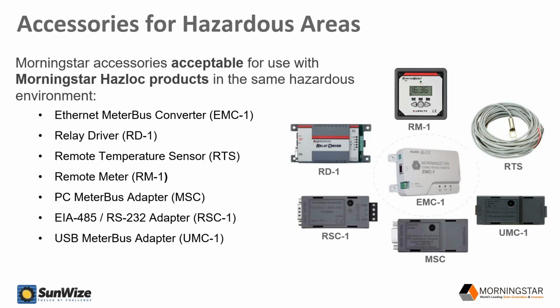In other words, these products have gone through the listing process and are part of the test report that Morningstar has to process in order to get these listings. So products that drive relays, such as the relay driver, or provide remote IP connectivity, such as the EMC1, have gone through this listing process with the host controller. So when the solar controller and these accessories are used together, they do comply with the listing requirements and can also be used in these applications, which is a pretty critical need because of the need for data.